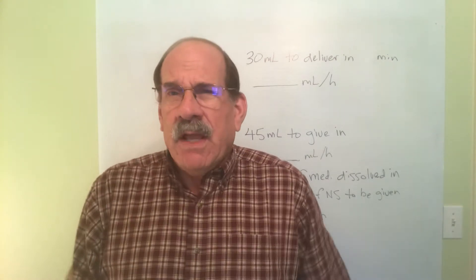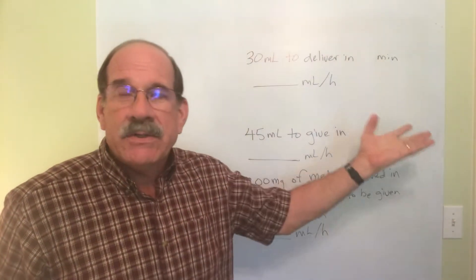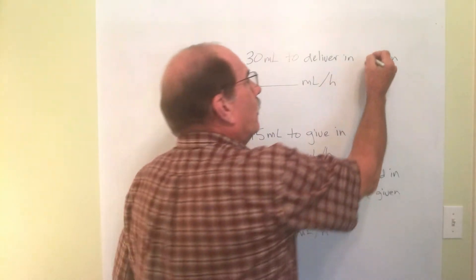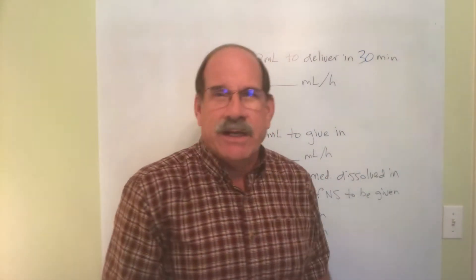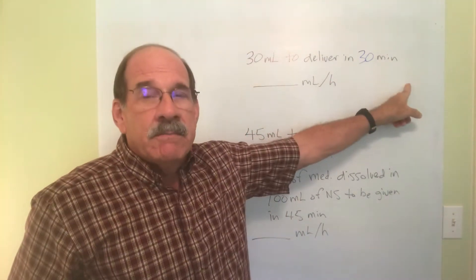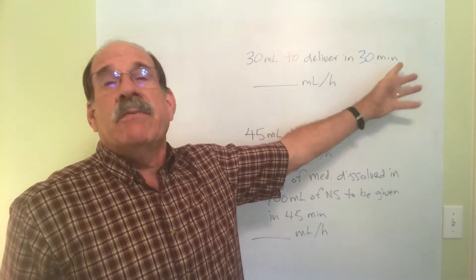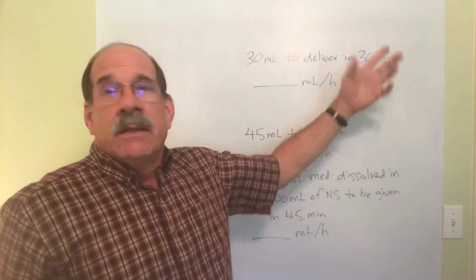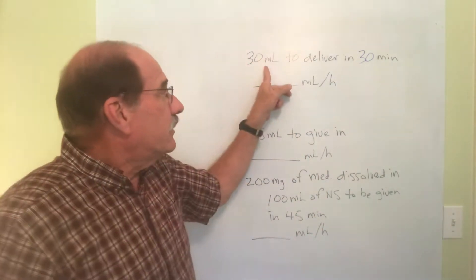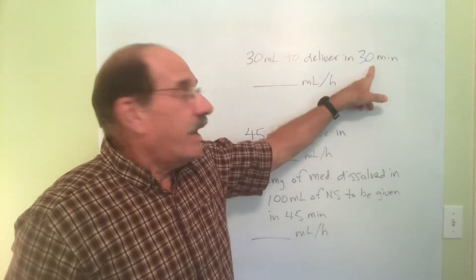From syringe pumps it's a small amount of medicine in liquid form over a fairly short time. For example, let's say we have 30 milliliters of some kind of medicine and we're going to deliver it over 30 minutes. This is less than one hour, so I'm not going to use the simple method of dividing milliliters by hours. Let's think this through first.